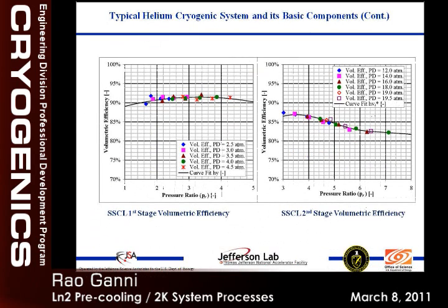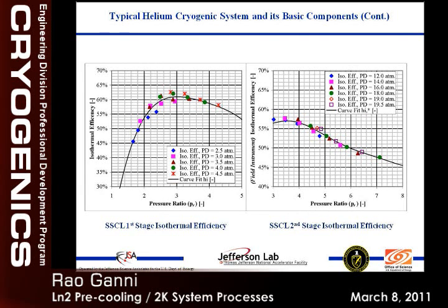So this is basically what we tested way back at SSC, a lot of compressors, to establish what the driving factors are in pressure ratio versus volumetric and isothermal efficiency. And this is what we're installing now as ESR2. We'll have the same machine which we brought, we just put it in there. When eventually commissioned, we'll have the same characteristics as all these tests. We should be able to reproduce it on ESR2 because that's what we have in the long range plan. And this is the setup.